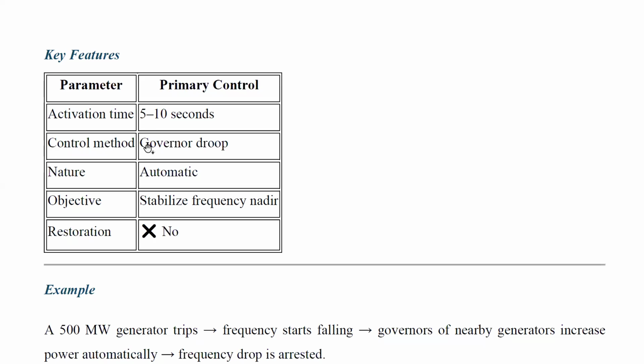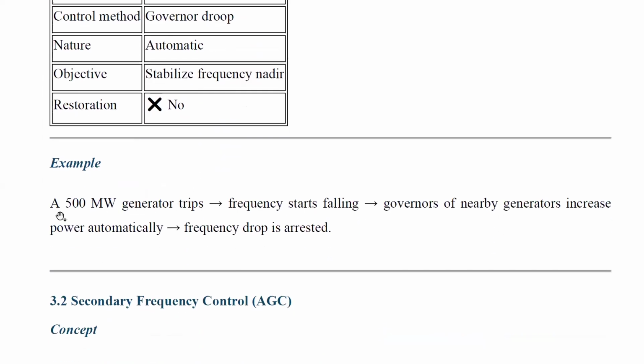If you take the control method, governor droop will do. Next, the nature is automatic. The objective is to stabilize the frequency deviation. Next is the frequency range. Next is restoration; in primary control there is no restoration. For example, if a 500 megawatt generator trips and the frequency starts falling, the governors of the nearby generators increase the power automatically such that the frequency drop is arrested. So these are the main mechanisms in primary frequency control.